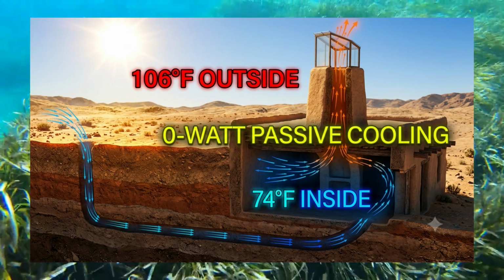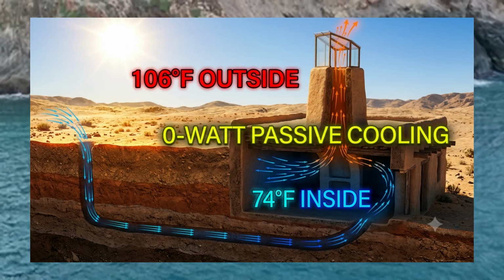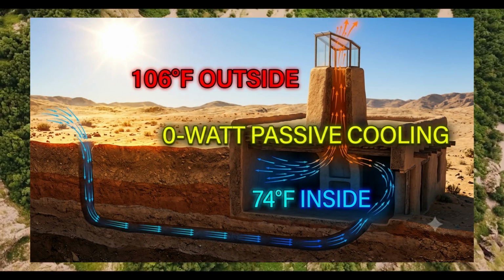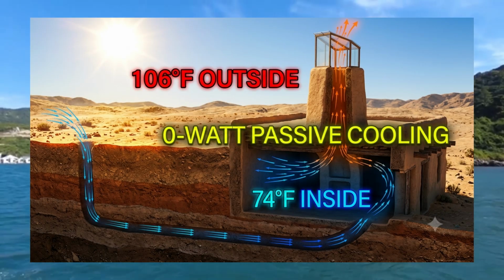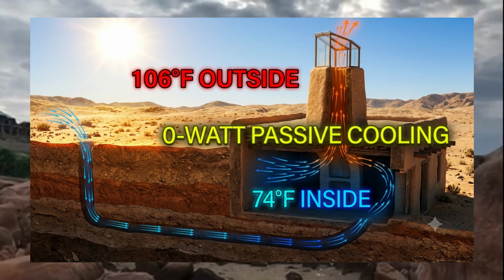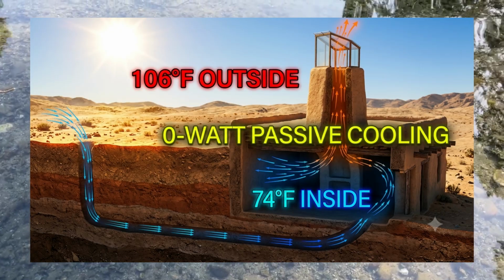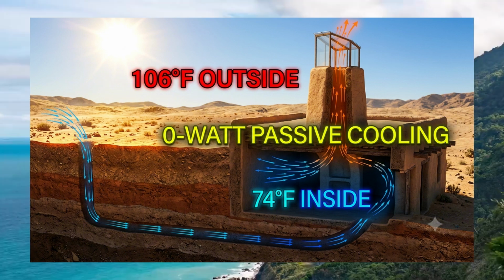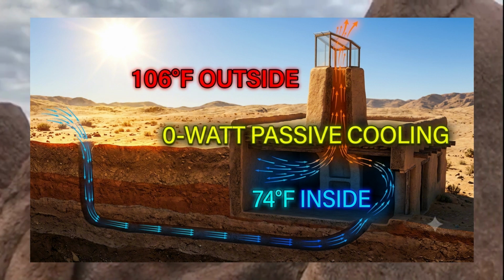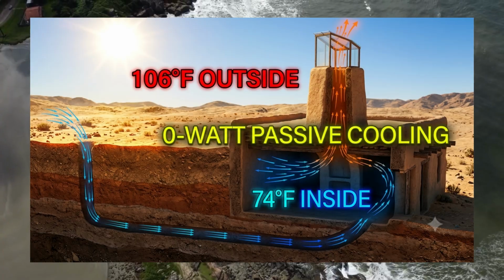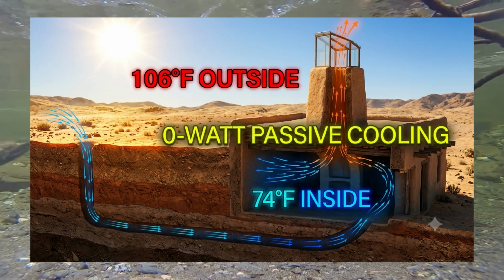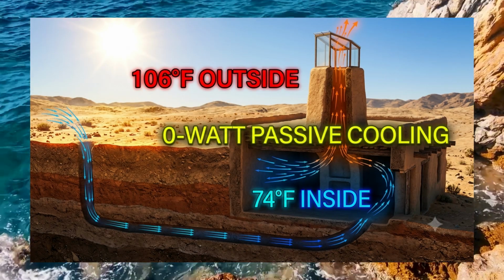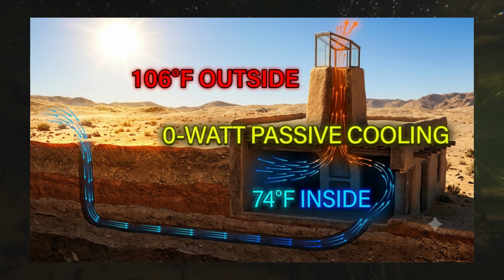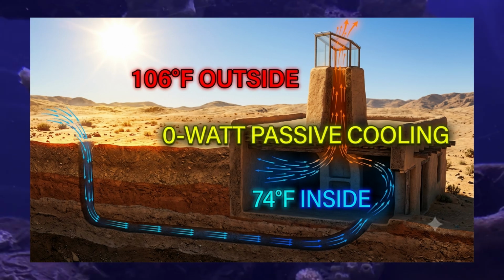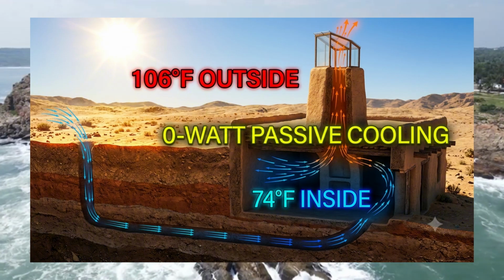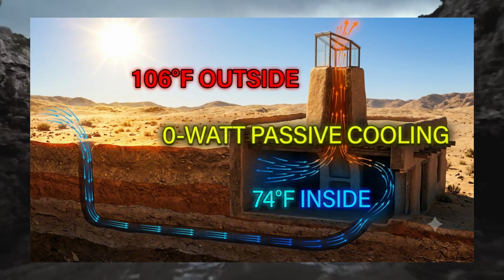If your home contains any traditional fuel-burning appliances such as a wood-burning stove, a propane space heater, or a gas-fired water heater, they rely on a natural, upward draft to carry dangerous combustion gases safely out of the house. These appliances operate on a very delicate pressure balance. The hot exhaust gases from a wood fire rise up the metal flue because they are lighter than the indoor air. However, if your solar chimney is pulling air out of the house faster than fresh air can enter through the subterranean tubes, the negative pressure inside the home will act as a stronger vacuum than the draft of the stove's chimney. The natural flow of the heating flue will stall.